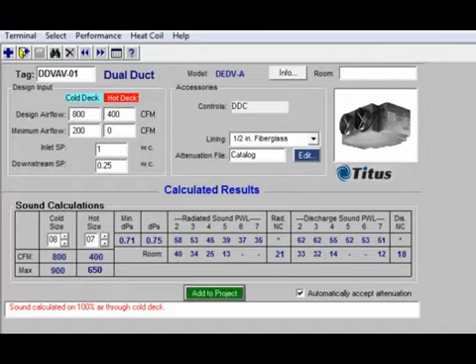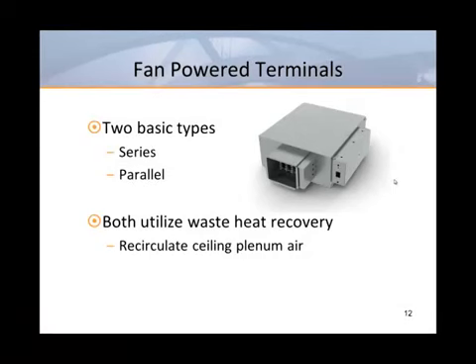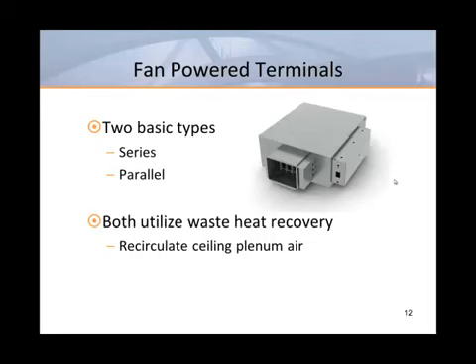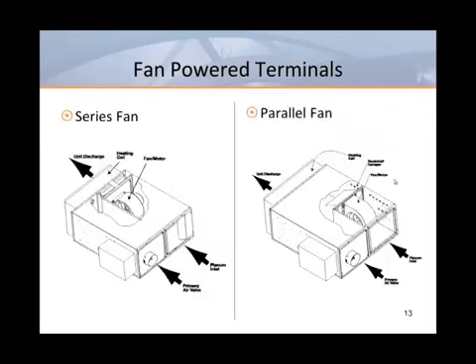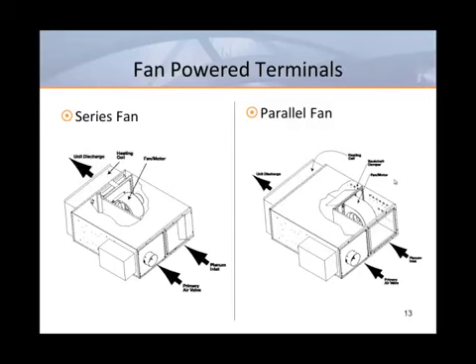Now let's look at fan powered units. Fan powered terminal units are available in two basic types, typically referred to as series or parallel fan units. There are other subcategories including quiet, ultra quiet, low profile, and units designed for under floor applications. The unit fan draws return air to be used as free heat and delivers it back to the space. In a series fan unit, cold primary air is delivered by an air handler to the VAV inlet. The unit fan runs continuously to deliver a constant volume of mixed air to the room, while the primary inlet regulates the amount of cooling and makeup air is pulled into the induction port.